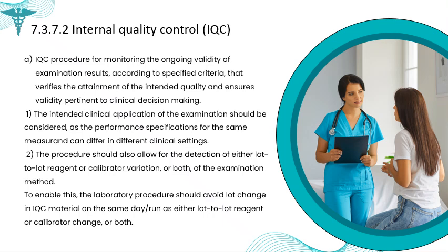The intended clinical application of the examination shall be considered, as performance specifications for the same measurand may differ across clinical settings. The IQC procedure shall also enable detection of lot-to-lot variation in reagents, calibrators, or both. To facilitate this, the laboratory shall avoid changing the lot of IQC material on the same day or run as a reagent or calibrator lot change.